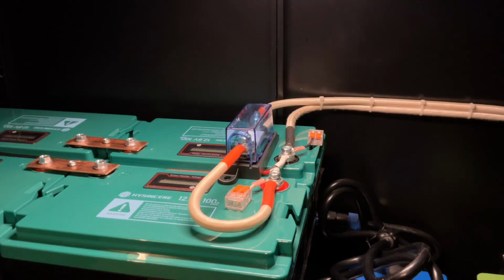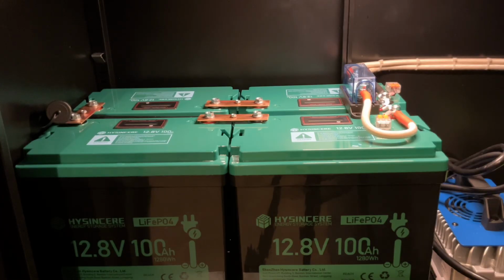48 volts DC is regularly considered safe to work around with dry, bare human skin, and generally it's not necessary to wear high voltage gloves to work on it. But a 48 volt lithium iron phosphate battery bank fully charged can exceed 58 volts DC. That, coupled with the fact that as you're working your body perspires, you have a little bit of a salty layer on your skin, and your finger can easily reach across that positive and negative battery post, which actually occurred as I was installing the fuse holder. I did not receive a huge shock, but I felt the tingle.